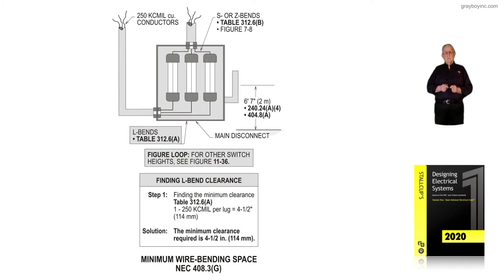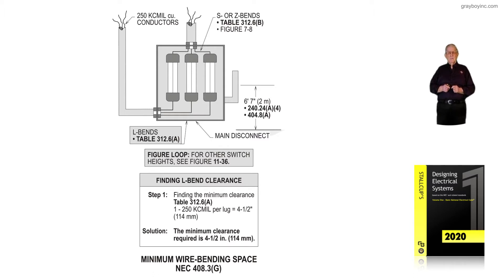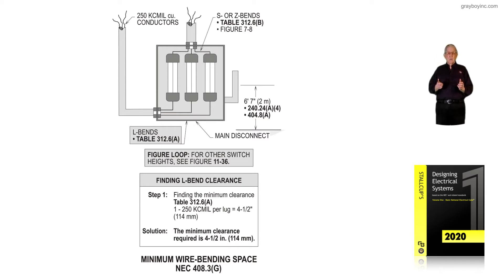This illustration deals with the minimum wire bending space in accordance with NEC 408.3G. Notice that when we enter into an enclosure, switch, or whatever it may be, we either have the conductors bent in an L-bend shape or an S or Z-bend shape.